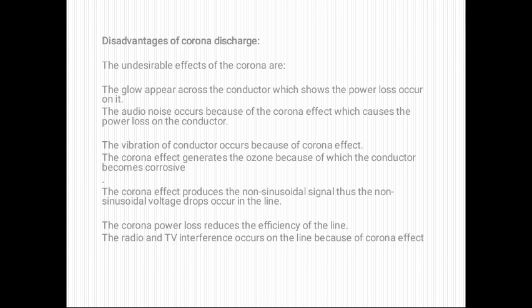Now there are some disadvantages of corona loss. First is the glow that appears around the conductor, which shows the power loss occurring on it. It means corona effect causes power loss in the line. Second is the audible noise that occurs because of corona effect, which also causes power loss on the conductor. Next is vibration of the conductor because of corona effect. The corona effect also generates ozone, because of which conductors become corrosive.